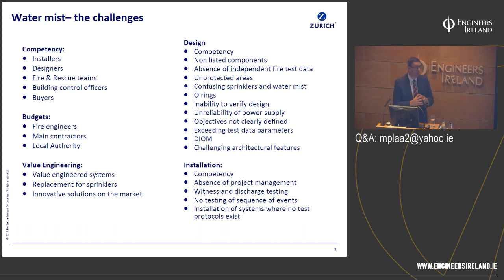And one of the big areas to be really careful of and to watch out for is witness and discharge testing. The vast majority of these systems are simply installed and never proven or commissioned correctly. I'll give you some great case studies later on where I found issues where the customer relied on a piece of paper, a certificate, to say that system was fit for purpose, and in most cases it isn't. I wrote an article for the IFE Journal in 2015 giving my experience of witness and discharge testing of water mist systems. 90% failure rate when tested. 90%. Okay, and I'll give you some examples of that.